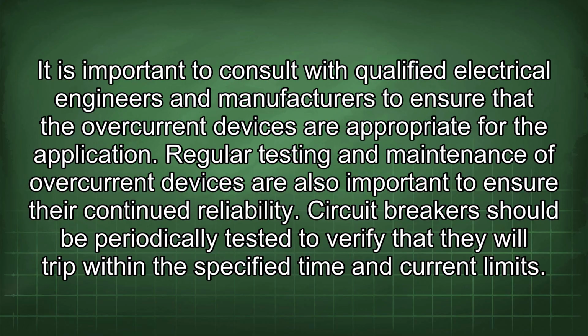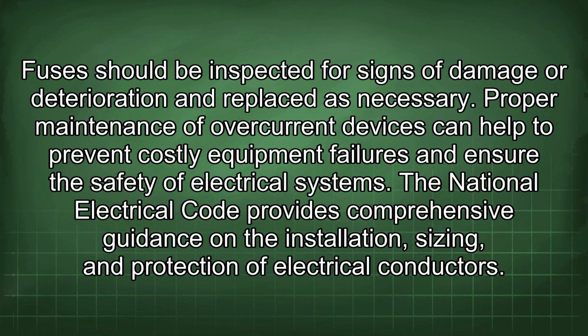Circuit breakers should be periodically tested to verify that they will trip within the specified time and current limits. Fuses should be inspected for signs of damage or deterioration and replaced as necessary. Proper maintenance of overcurrent devices can help to prevent costly equipment failures and ensure the safety of electrical systems.